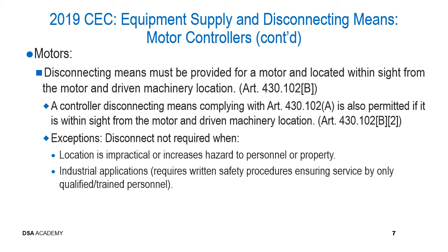Now, there again are exceptions, as is very common in the California Electrical Code. A disconnect is not required when, number one, the location is impractical or increases hazard to personnel or property. And in industrial applications, these require written safety procedures ensuring service by only qualified and trained personnel are provided and available.